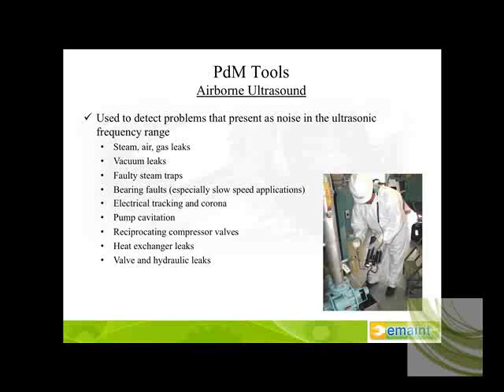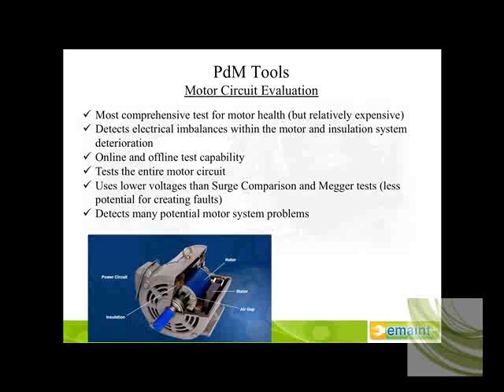Now on to motor circuit evaluation. You heard me mention earlier that vibration analysis can point to some AC, DC, motor and control problems. Motor circuit evaluation really is your most comprehensive tool for motor health. However, again, it's a fairly expensive tool to get involved in. It has the capability of detecting electrical imbalances within the motor and the insulation system. It is comprised of both online and offline testing. It tests the entire motor, everything inside of that housing, including the insulation. One of the nice things is it uses lower voltages than surge comparisons or megger tests, so the use of motor circuit analysis actually has less of an opportunity to create its own faults.